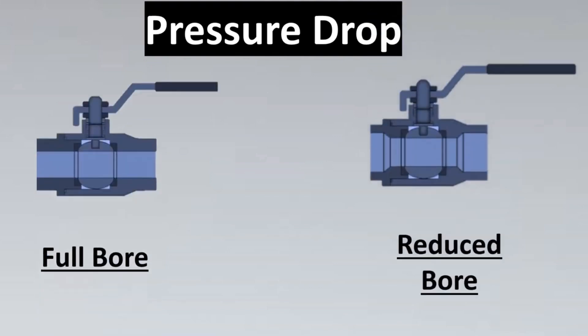The next consideration is pressure drop. Between full bore and reduced bore, the reduced bore valve will have a higher pressure drop because the bore size is smaller, causing some restriction to the fluid. This pressure drop is not high, but you still need to confirm with the process team that they are okay with such pressure drops throughout the system, or that they have compensated for them.